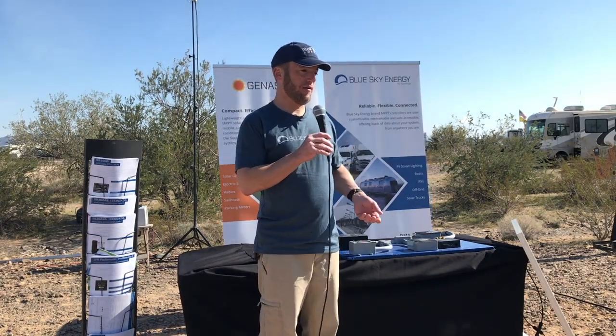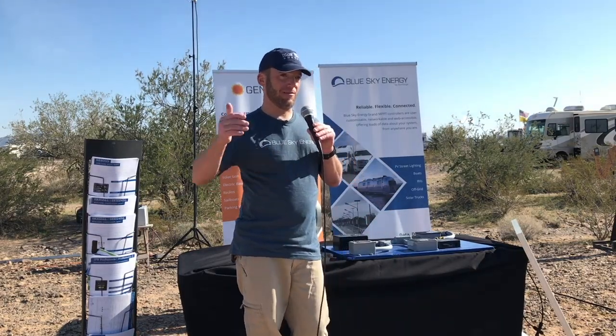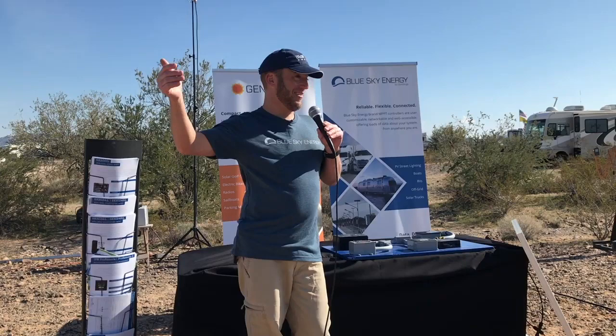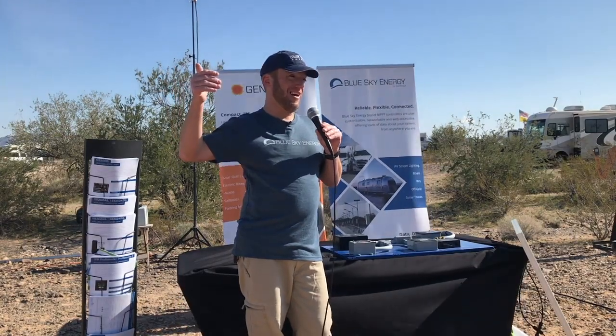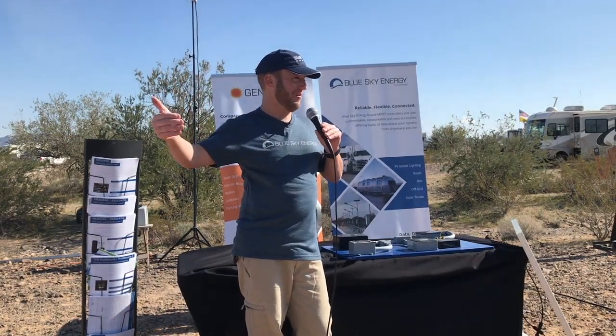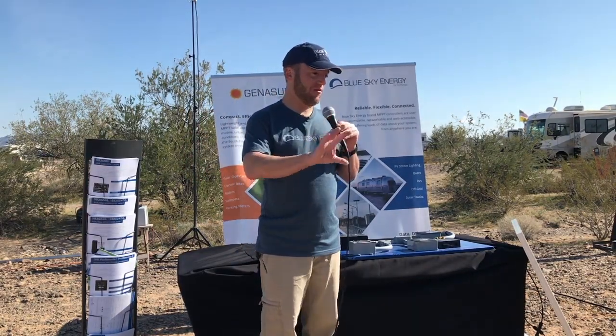There's a lot of situations where people want to put over 150 or 170 watts, or situations like panels out in Alaska where, when the sun's really low in the sky, you need a ton of panels connected just to get 10 amps, but in the summer one panel would be fine. What do you do? In that situation we just reduce the current limiting on the firmware, and that way you can use it all day long and it won't ever give any trouble with excess PV input. It would never damage the controller.